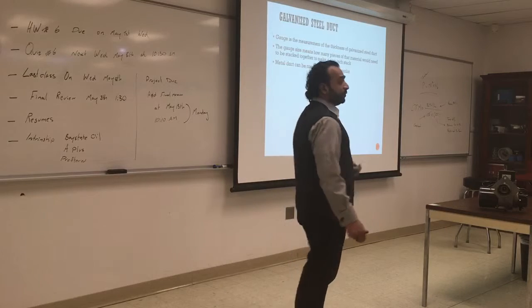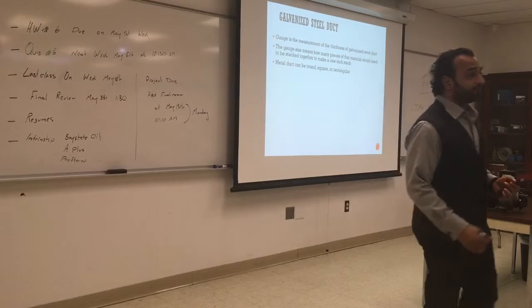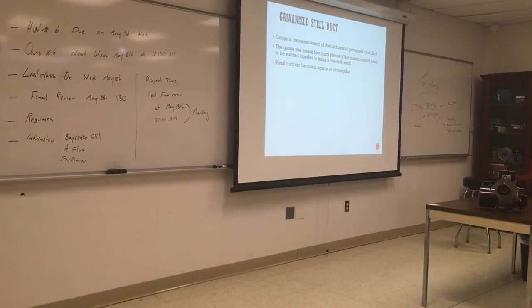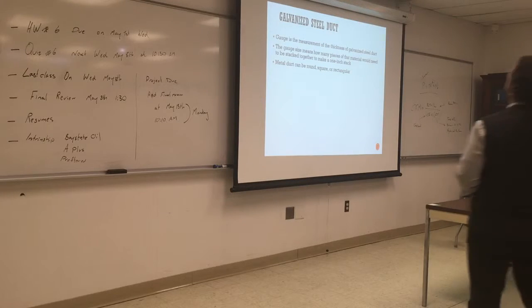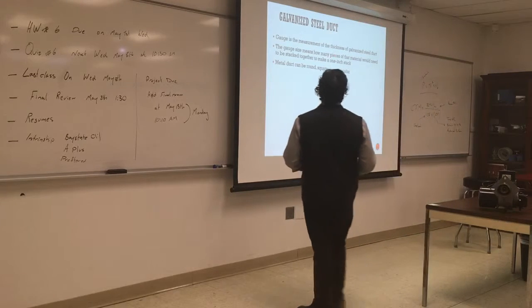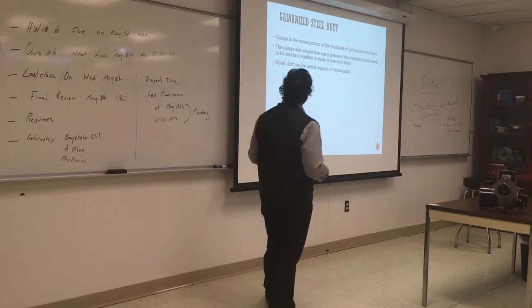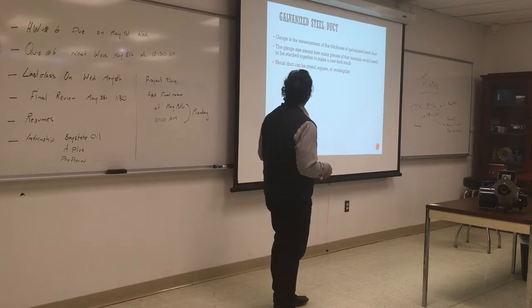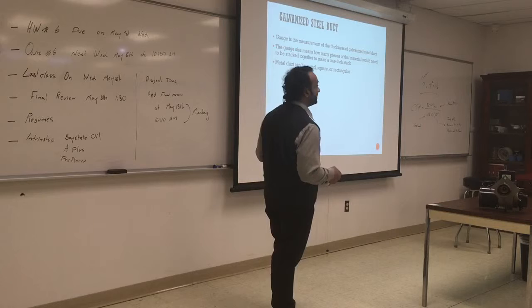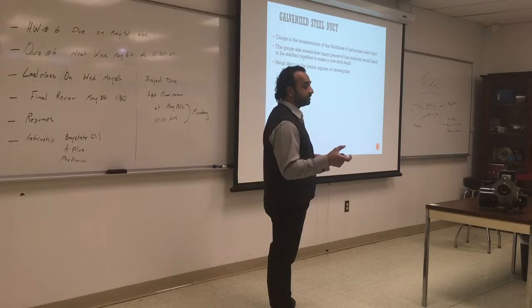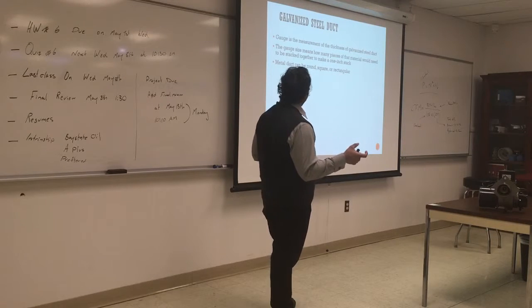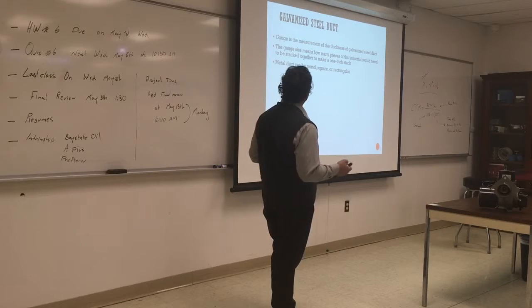So gauge, when we look at galvanized steel, they give you the gauge. The gauge is the thickness of the metal, and that thickness has to do with the size of the duct, so it does not collapse, it does not wobble, and it can hold shape. We need to understand what the gauge size means. Thicker gauge means it's a thicker sheet metal and can support more weight.